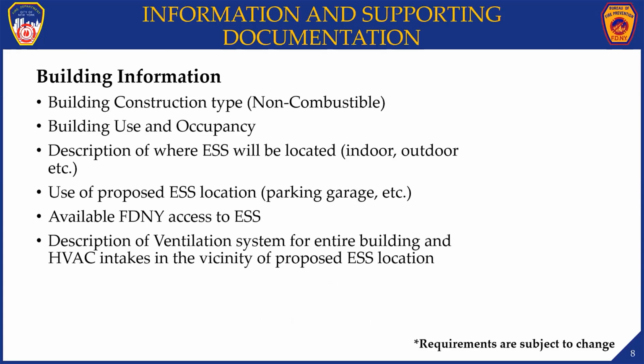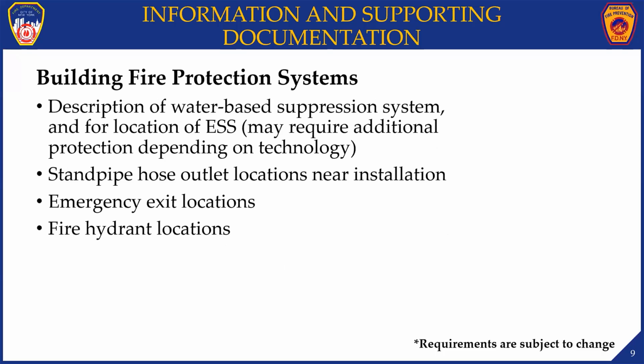When submitting a TM1 application, it is crucial to provide certain information for the review process to be as efficient as possible. Based on the battery chemistry and charge density of the ESS, information that needs to be provided will vary. For installations on rooftop or inside buildings, we need to know the construction of the building, where the ESS is located, how will FDNY have access to the ESS, description of the ventilation system, if there's any HVAC intakes in the vicinity of the ESS location, the water-based suppression system, if required, standpipe outlet locations near the installation, emergency exit locations, and if there's any fire hydrants in the area.